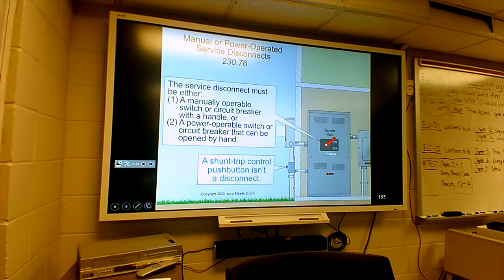there was a limit switch on the door, and when you opened the door, the limit switch would activate the shunt trip, and the shunt trip would trip the main breaker. It would trip the main breaker and kill the power to the machine. So there's no way you can go in that panel and get electrocuted because it would cut itself off. So a shunt trip is basically a coil, like on a motor starter. It's a solenoid type thing.